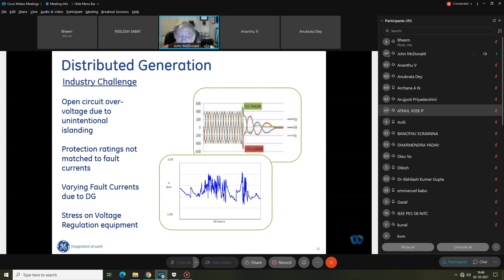Also, the load side contribution, the fault currents due to distributed generation, are varying, right? They're changing because of the intermittency of the renewable, of the distributed generation. The sun isn't shining all the time. The wind isn't blowing all the time. So the load side contribution to the fault varies due to the intermittency. That complicates things even more. Okay, and then we'll talk more in a little bit about the stress on voltage regulation equipment.